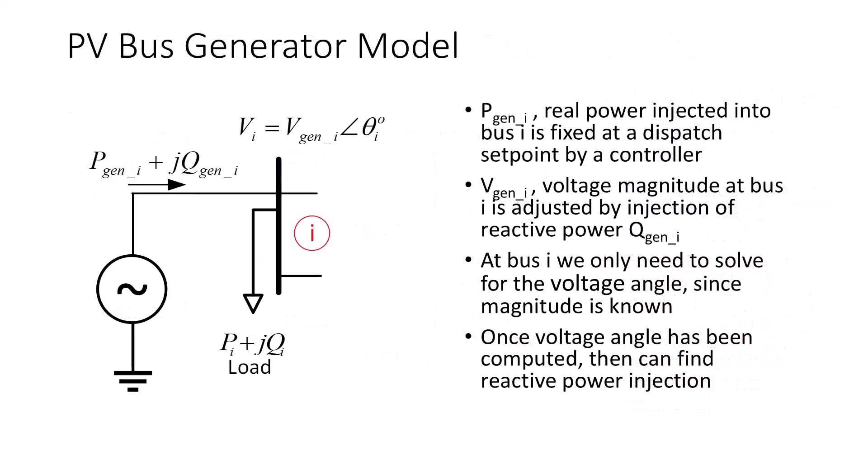Let's take a closer look at the PV bus generator model as connected to bus I. We will also model a PV bus local constant power load. The real power injection, PGen, is a known quantity that is specified in the input bus data set. The voltage magnitude, VGen at bus I, also needs to be specified. Since voltage magnitude is known, then we only need to compute the voltage angle theta at a PV bus. The reactive power injection, QGen, is computed once the voltage magnitude and angle are known.